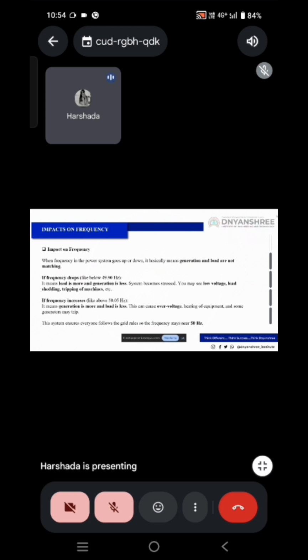If frequency drops below 49.90 hertz, it means load is more and generation is less, so the system becomes stressed. You may see low voltages, load shedding, and tripping of machines. If frequency increases above 50 hertz, it means generation is more and load is less. This can cause over voltage, heating of equipment, some generators may trip, and losses like I-square-R copper losses occur. This system ensures everyone follows the grid rules, so the frequency stays near 50 hertz.